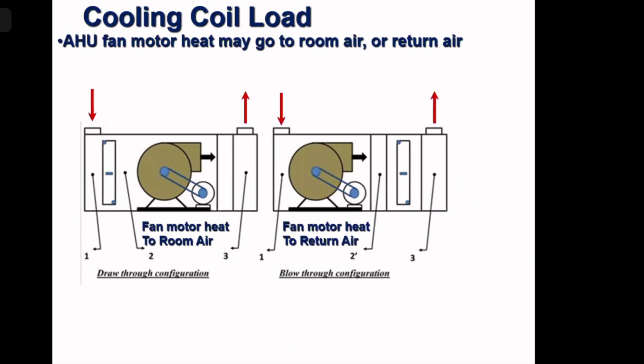I have shown two types of air handling unit. You see, by red lines, I have shown return air coming inside the air handling unit, return air plus outdoor air coming inside the air handling unit, and the other one is the supply air. Now, for the left one, left air handling unit, first we have the cooling coil, then fan, then outlet. There will be filters, etc., which is not shown. And the second one, you see, we have fan and then cooling coil. Return air, then fan, then cooling coil, then it goes out.